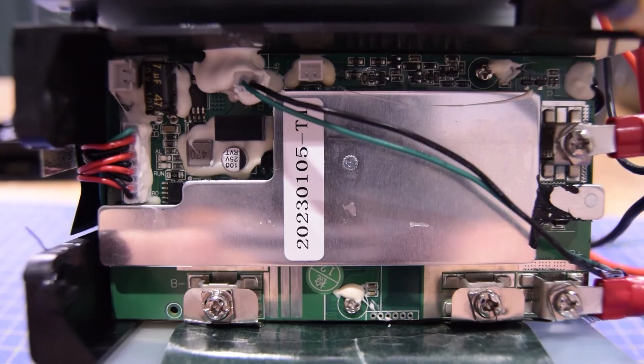But this is also paralleled up with the input, which is kind of cool, because it goes back to what I was saying about using this like an online standby UPS. The charging controller can choose not to charge the batteries, and you can use that rectified power coming straight out of the rectifier, so you're not cycling your batteries or adding to their life cycle. The charging controller can choose how it lets that cycle go, how low or high it discharges them, and monitor that voltage the whole time. That's awesome, actually. That's very cool.